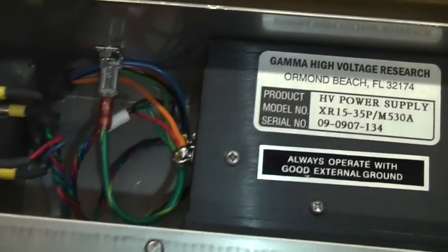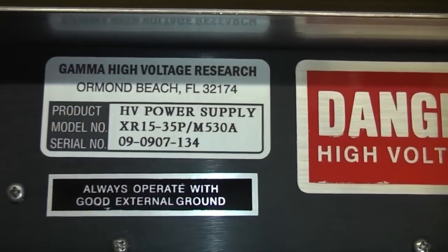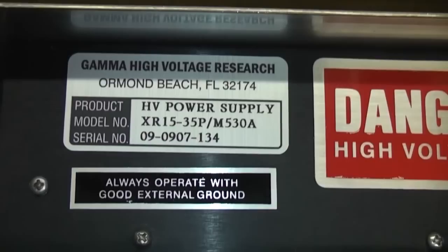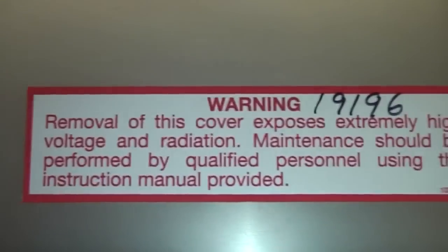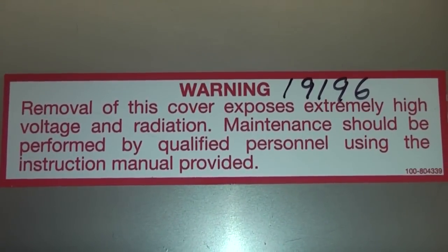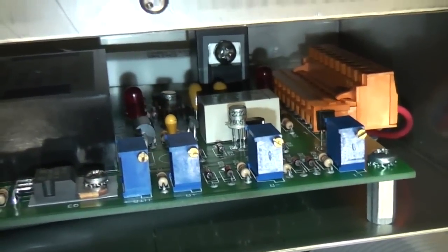Obviously in the middle, this is the actual X-ray tube assembly. And in here we've got the 35 kV power supply. Big warning on radiation and high voltage. And there's a control board here, so that's going to be doing some of the control of things like the voltage and current regulation, but also because the microfocus X-ray tubes use magnetic focusing, this is probably going to be doing some of the driving of the focus coils, etc.